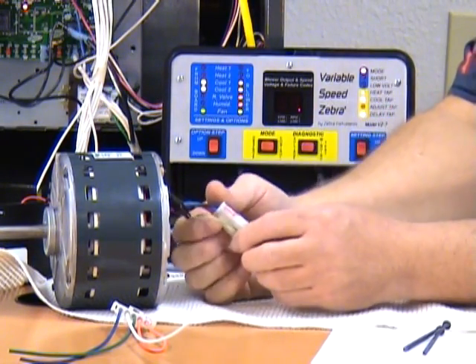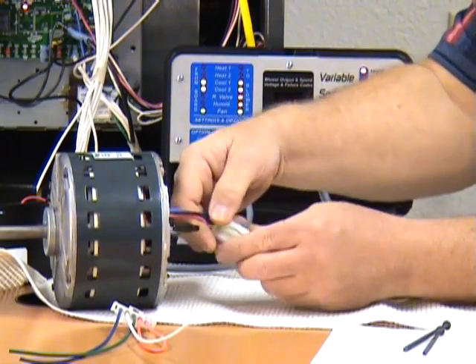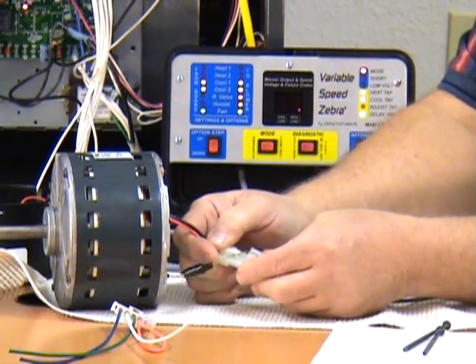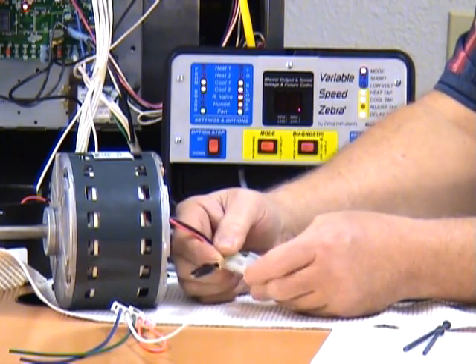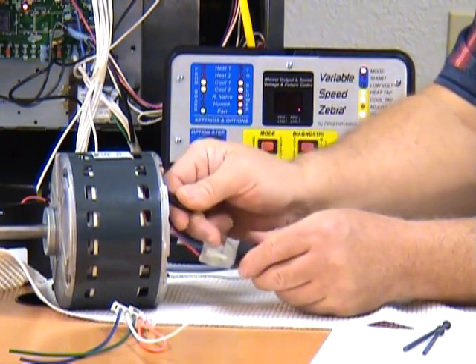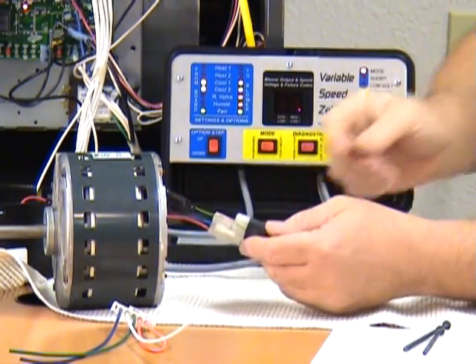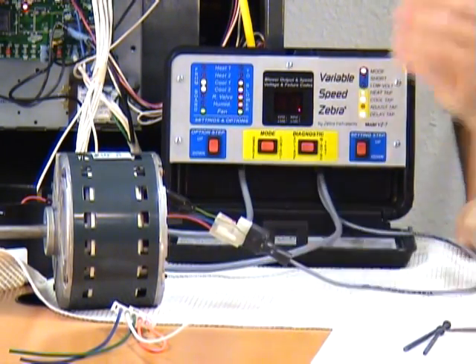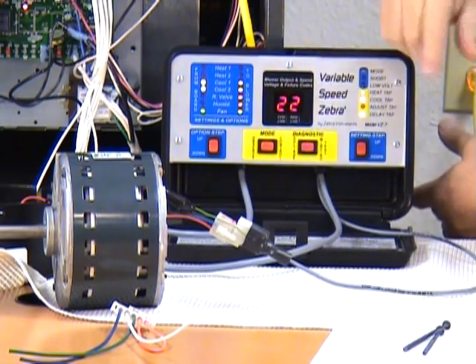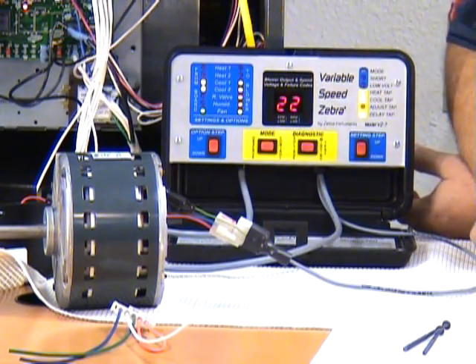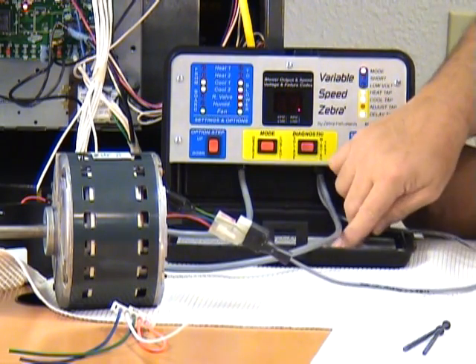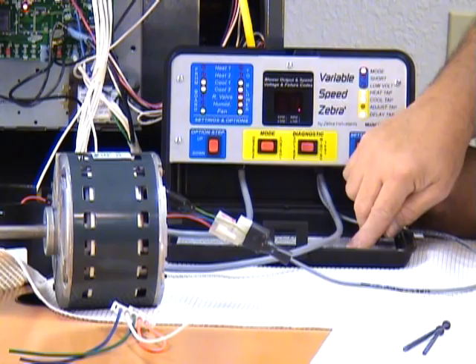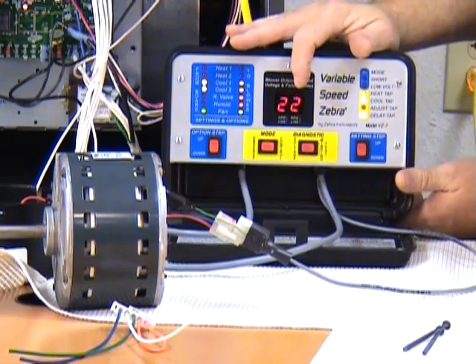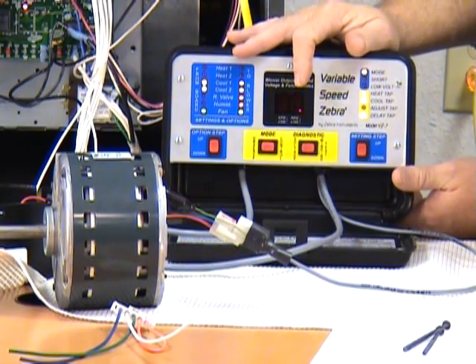Let me demonstrate how this test might show. For instance, you can plug this plug in incorrectly if you only plug in 2 wires of it. So I'm just going to demonstrate what happens if we leave one wire not connected like this. We'll ask it to do a winding test. It won't even ask us to spin it because it's already determined with a code 22, which says that phase B on that motor is open. It's already determined that there's something wrong with it. It stops at the very first failure on that motor. So it says, hey, there's a winding open, buddy. You don't even need to spin that thing. I can tell you you're going to need to replace it.